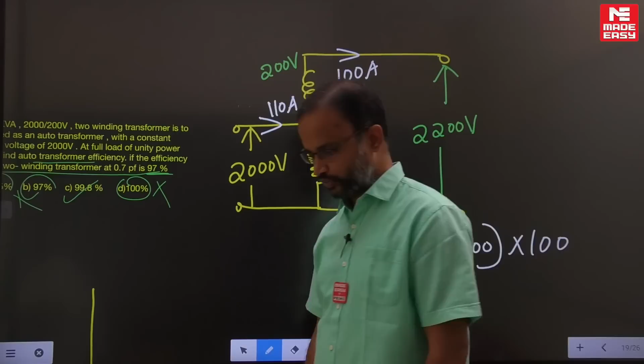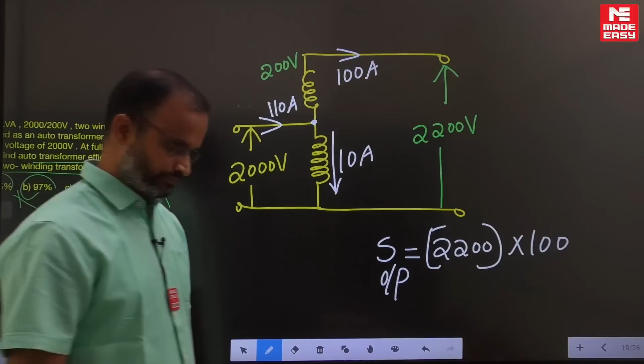Every time, the voltage ratio is inversely proportional to the current ratio. That's why the low voltage side current is greater compared to the high voltage side. You can calculate the same S value from this also. And one more point.